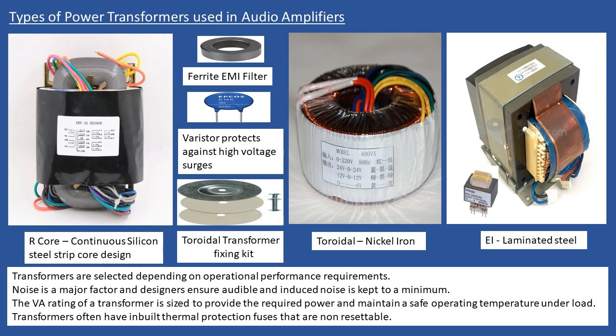Now with the EI type transformer, in this example you can see that there's a copper shield which is going around the center section, then connected to the metal work of the transformer, and we'll describe how these are manufactured in a little while. And what's happening there is that they've put an RF filter or a radio frequency filter just to prevent noise either entering into the transformer, and equally so all transformers generate some level of electromagnetic interference because of their operation, and they're just preventing that from radiating out.